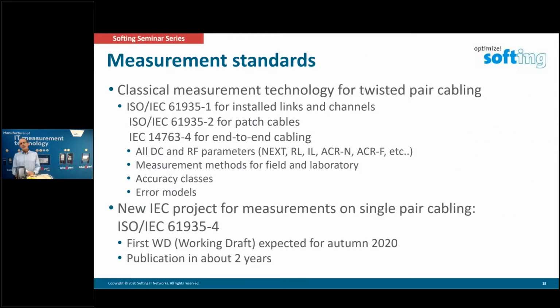Now the really interesting part from a testing point of view is the measurement standards. Our testers, the certifiers, work according to ISO IEC 61935-1 for installed permanent link and channel measurements, installed cabling. There's another standard, the -2, for patch cables. The 14763-4 defines testing of end-to-end links. All these standards define the DC and RF radio frequency measurement parameters like NEXT, return loss, insertion loss, ACRN, and so forth.